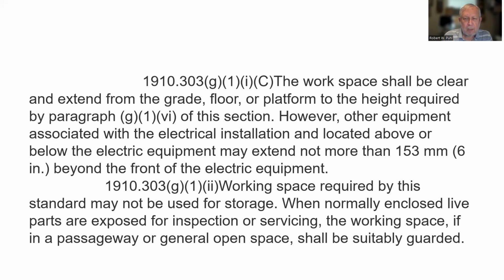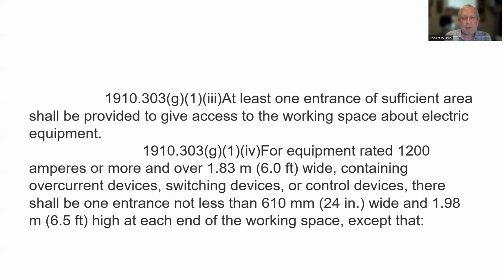Okay. Working space required by the standard may not be used for storage. When normally enclosed, live parts are exposed for inspection or servicing, the working space, if in a passageway or general open space, shall be suitably guarded. So that we're normally enclosed. So if you have to open up the space, then that space has to be guarded, because if it's just where people walk by, they shouldn't be walking by while somebody's doing some work on it.